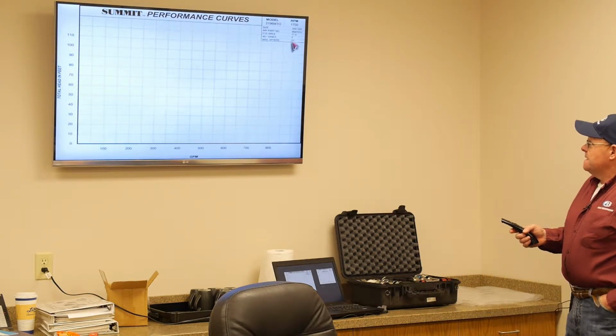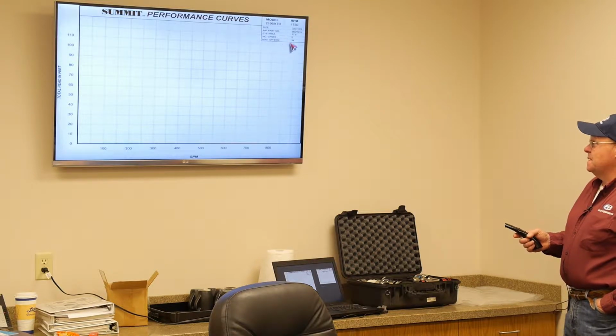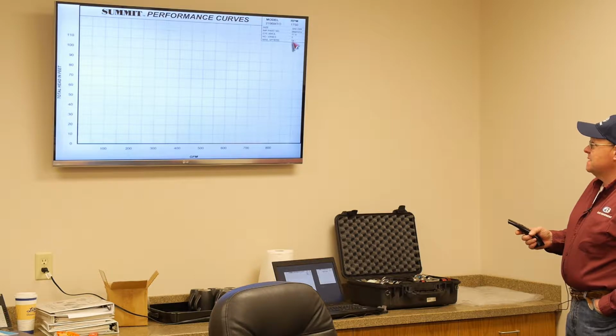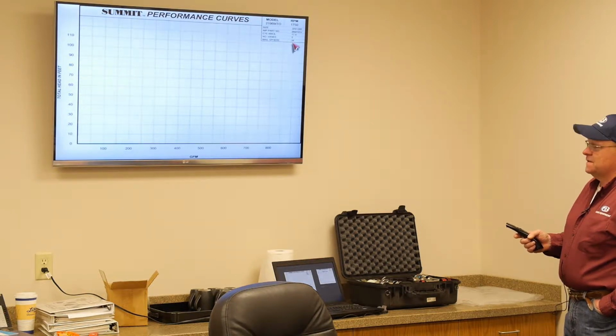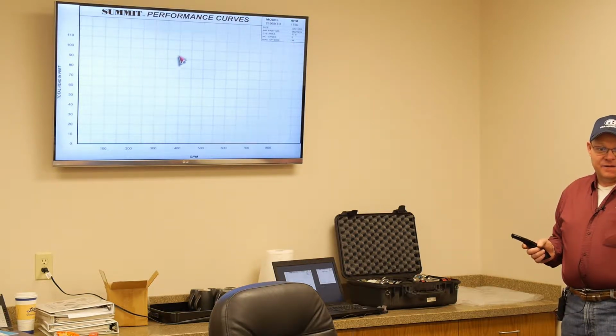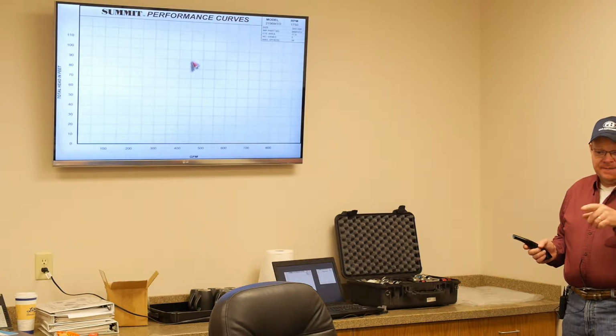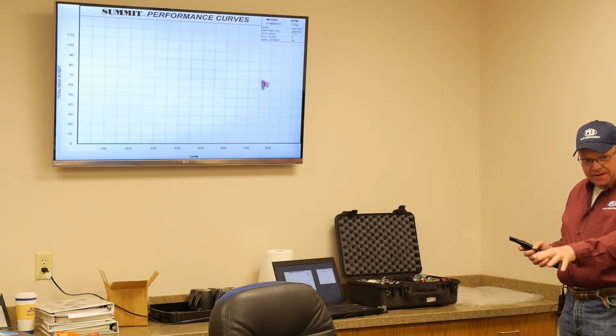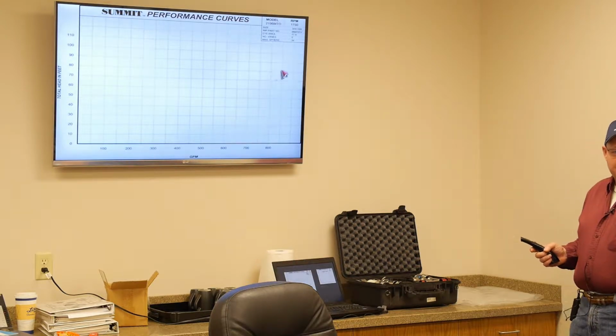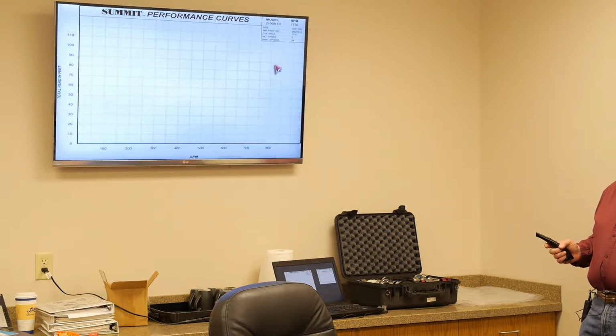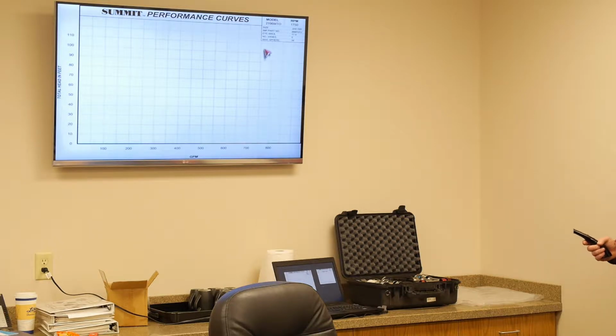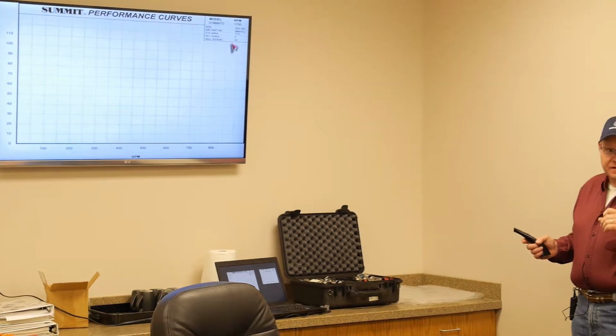And it gets down here, and this is the key part for some of you folks because they think it makes a difference. But anyway, max spherical size is 0.34 inches. Just a little bit bigger than 1/4 of an inch is the biggest solid that impeller, not that one particularly. Actually, it is that one right there. That is a 3410 impeller that's on there. The biggest spherical solid that pump will pass is 0.34, just a little bigger than a 1/4 inch ball. So that's that information there.